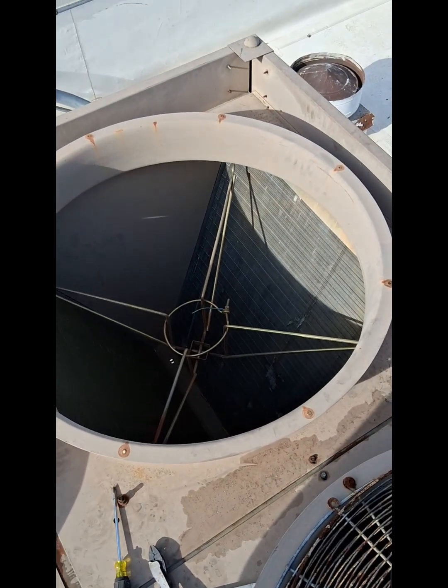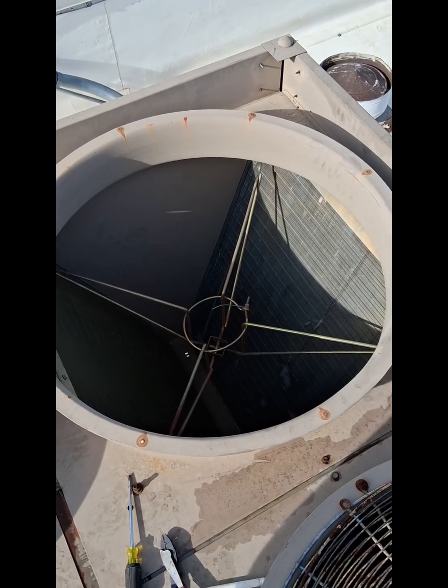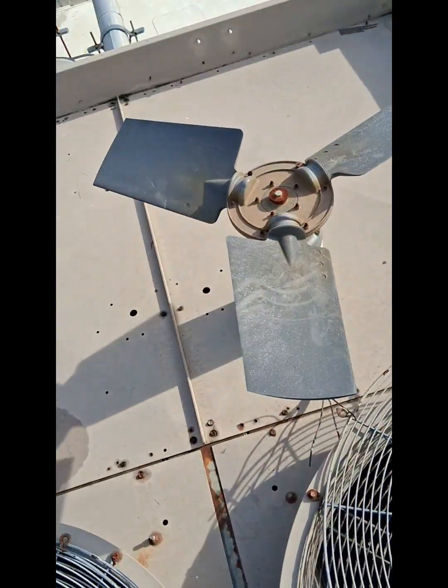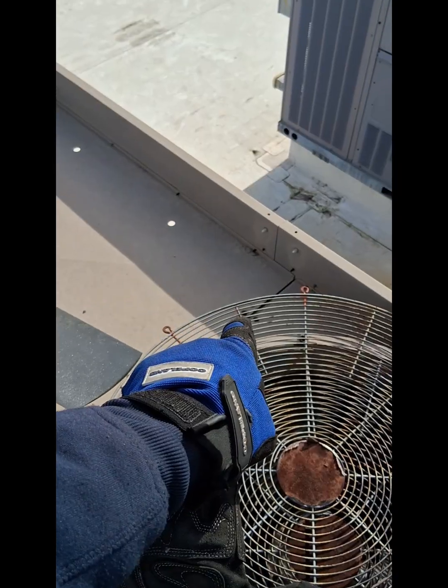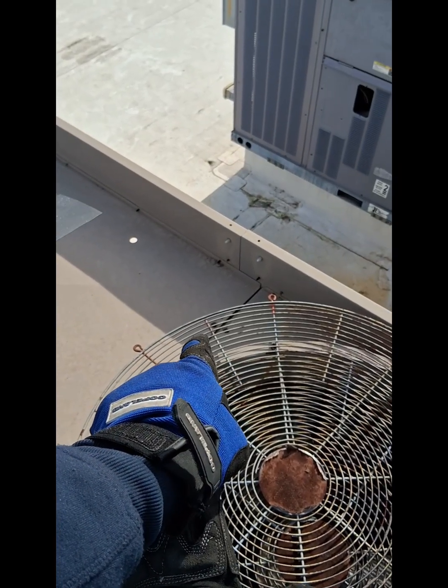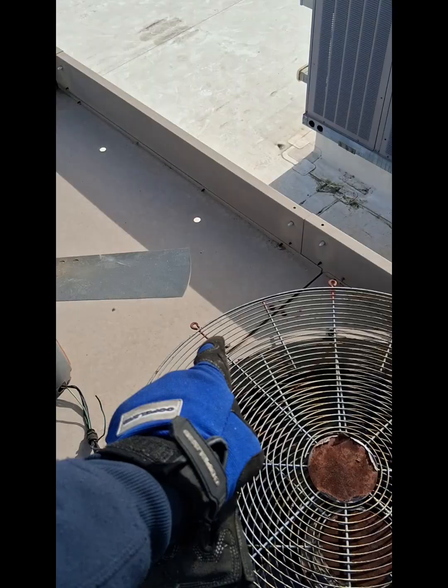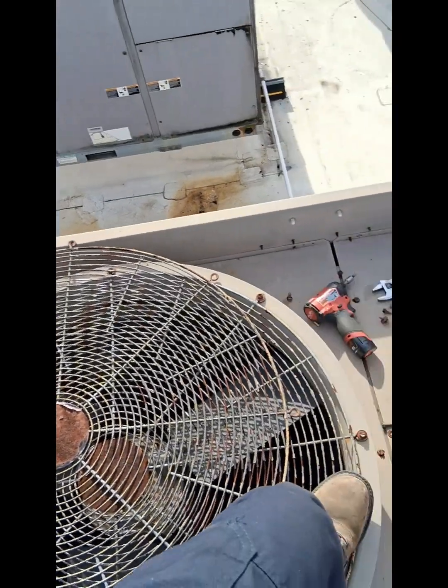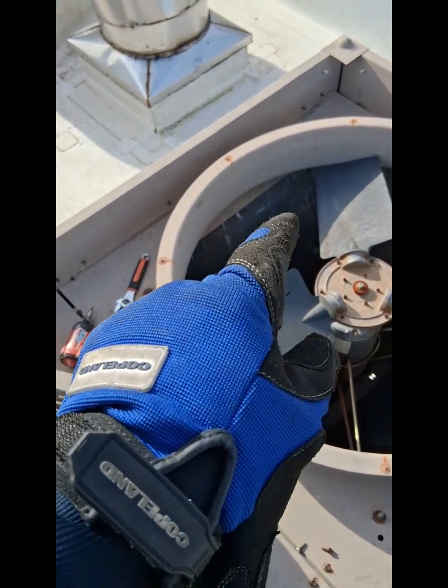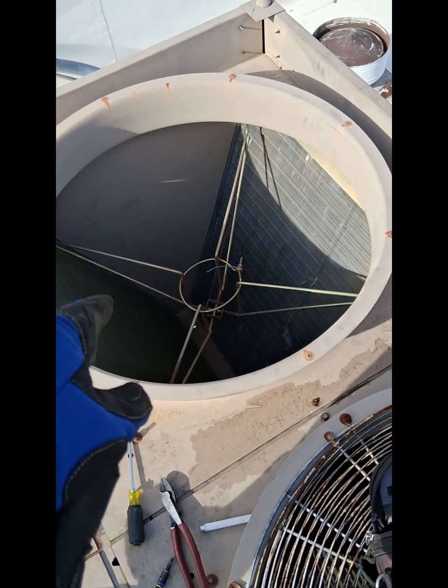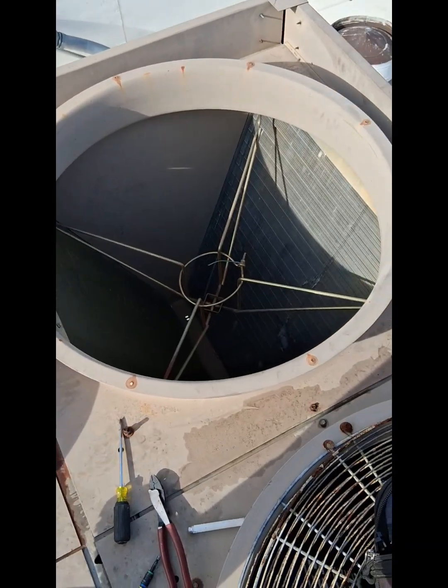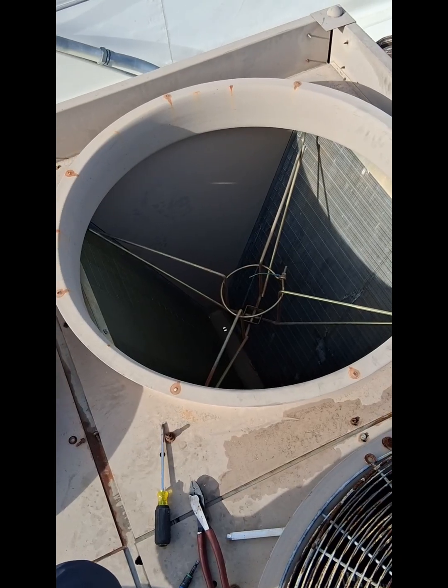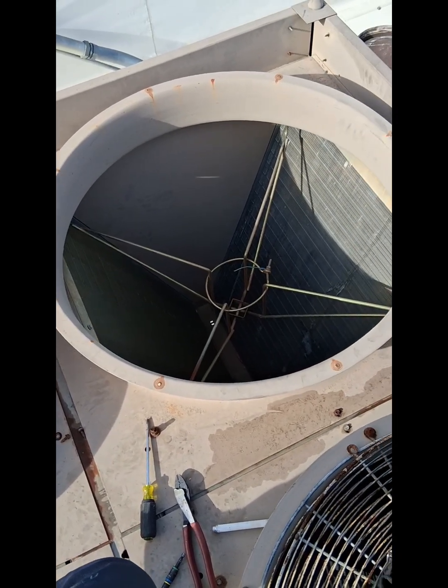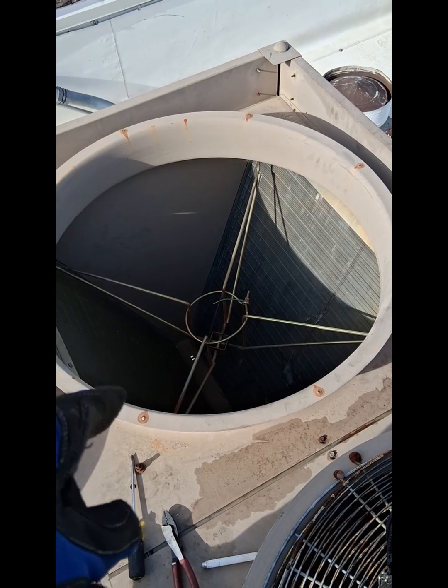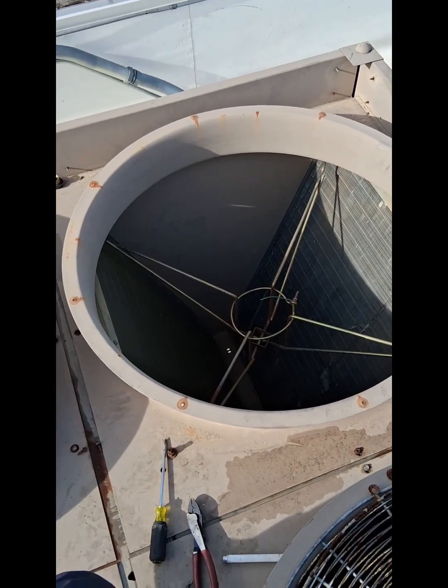I am having to swap fans from one circuit to the other because that fan motor is bad, and I believe circuit 2 has a bad, no, circuit 1 has a bad discharge pressure transducer. So I'm taking the fan off of circuit 1 and putting it on circuit 2 because circuit 2 has a bad fan, and it has blown like a fuse on each circuit. So I gotta take the fuses and put them on circuit 2 to get at least one circuit running so I can make some more repairs.